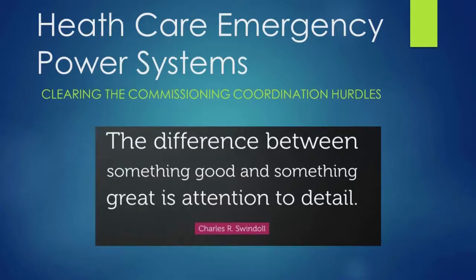There is a generator cool down mode, and it can be controlled either through the ATSs, the generator control module, or the paralleling gear, depending on the system. If you have an older system without an engine control module, the paralleling gear or transfer switch handles the cool down mode, typically programmed between 5 and 10 minutes. If you have a newer generator set with an engine control module, it no longer uses a timed setting but monitors internal temperature. Once it hits a certain temperature, it determines it's cool enough and shuts the generator off.